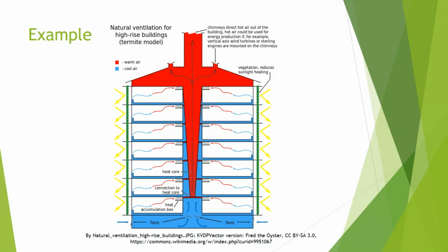The termite mound strategy uses fans to bring cool air in, and there's a lot of thermal mass in the core. The cool air comes in low and is distributed through all of the spaces, picking up heat in each individual space, then funneled into a heat exhaust that goes up through the core using natural ventilation. The chimneys essentially pull the hot air up and out, while fans bring fresh, cool air in. As a consequence, these buildings don't require extensive mechanical systems to maintain comfortable temperatures—using about 10% of the energy of a comparable building. These are the kind of strategies that can be employed.